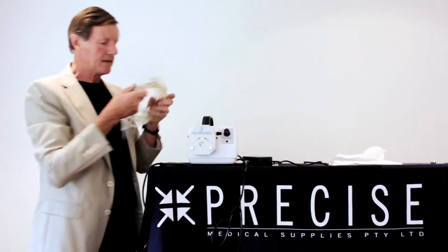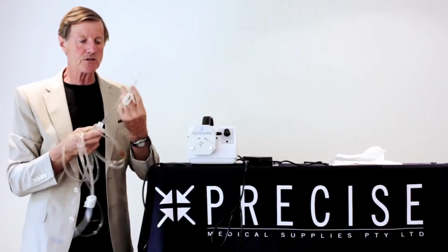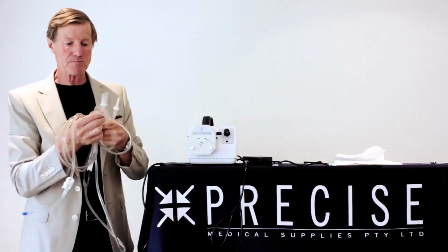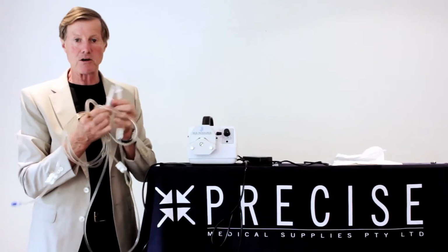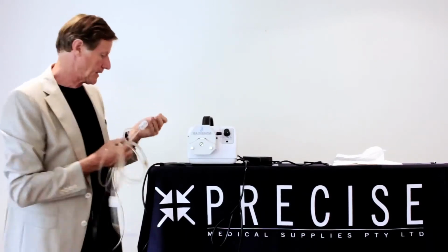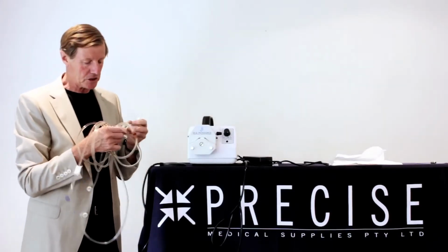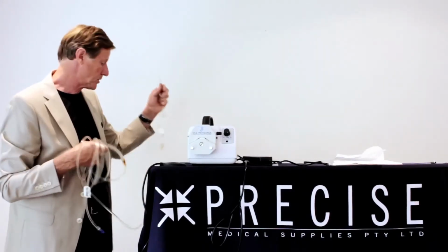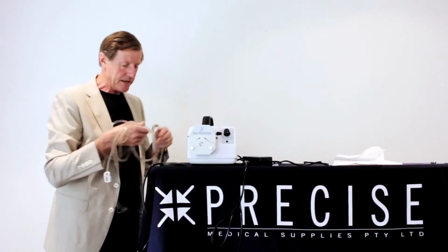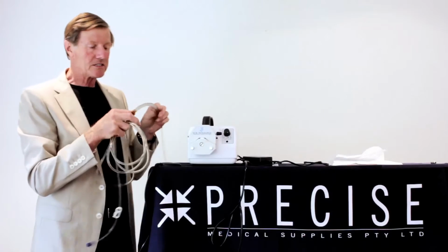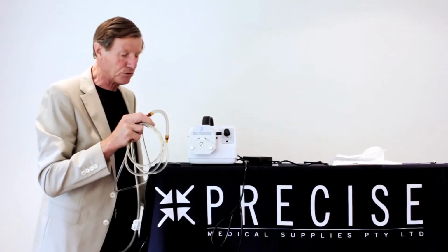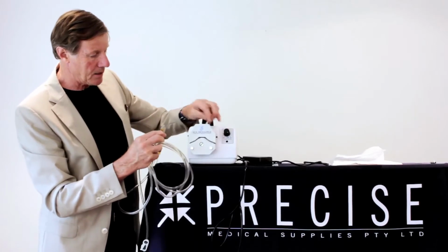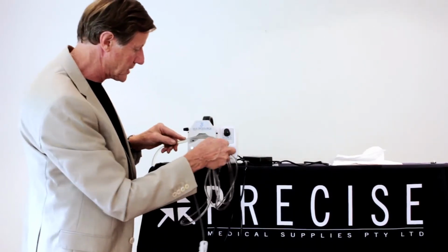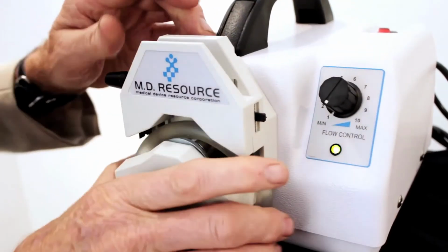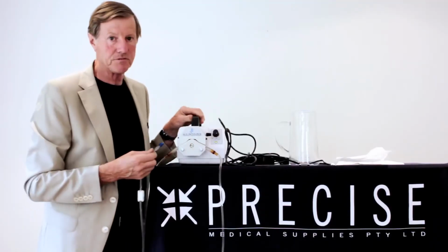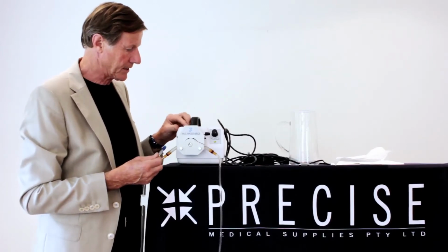Now the tubing has several sections. The first thing to note is the two spikes that will go into your bag of saline. These have clamps on them, and I'm just going to, for the sake of this demonstration, drop these into a container of water. I have that here. The next thing to note about this tubing is that there is a silicone section, and this is the section that will fit into the impeller on the peristaltic infusion pump. So just clamp it down with this lever here onto the peristaltic infusion tubing, and that will make a nice tight fit against the impeller.